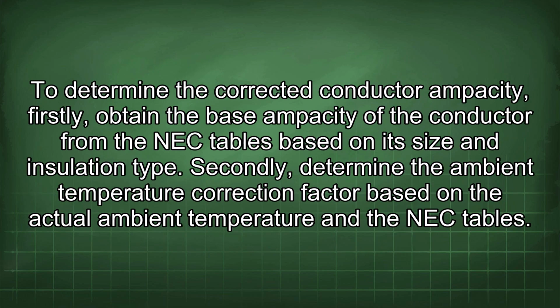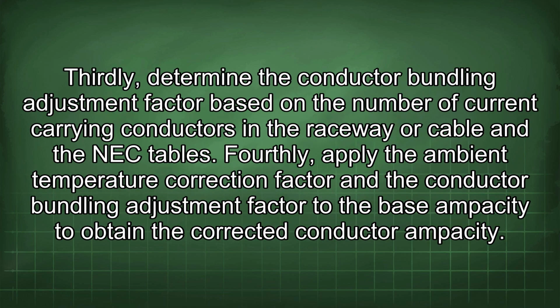To determine the corrected conductor ampacity, firstly, obtain the base ampacity of the conductor from the NEC tables based on its size and insulation type. Secondly, determine the ambient temperature correction factor based on the actual ambient temperature and the NEC tables. Thirdly, determine the conductor bundling adjustment factor based on the number of current-carrying conductors in the raceway or cable and the NEC tables. Fourthly, apply the ambient temperature correction factor and the conductor bundling adjustment factor to the base ampacity to obtain the corrected conductor ampacity.